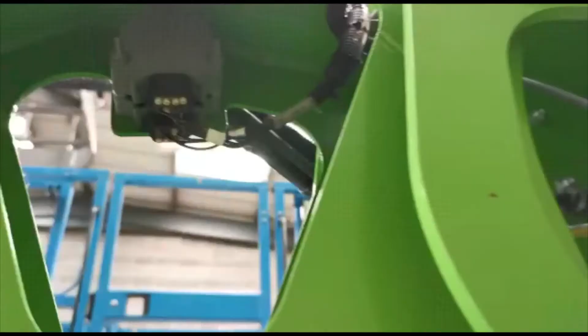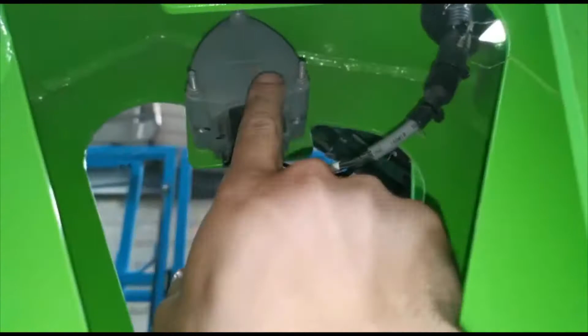Let's have a look. Okay, so this is the sensor. So I need the light on. So what I think, one of the sensors is the wrong way around. It should be reading the same, but on one sensor this part is facing out, and on the other sensor it is facing toward that side. So I think they're reading opposite angles. That's why the output is 2.2 on one and 2.7 on the other one. So I will try to refit this sensor. I think this one is the wrong way around. Okay, and we will continue from there.